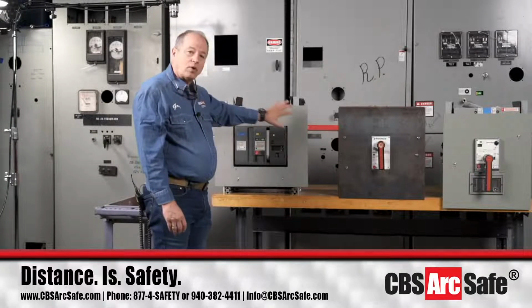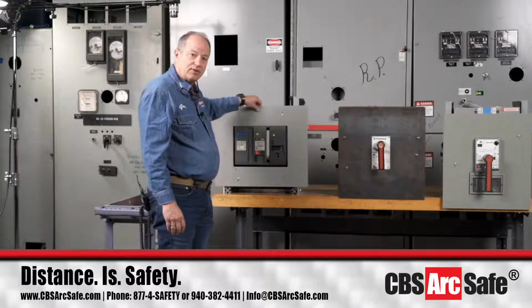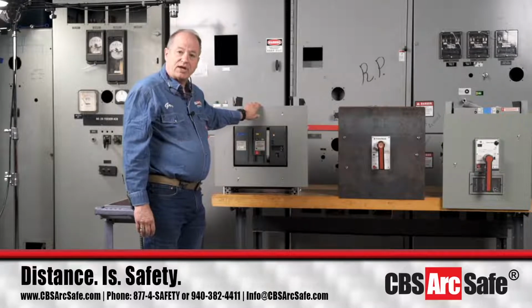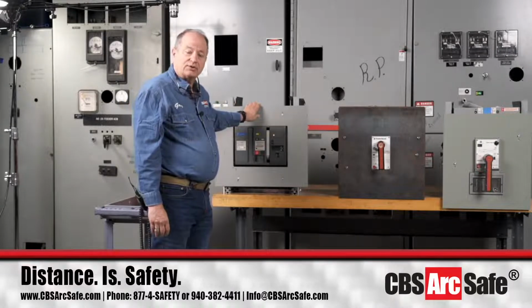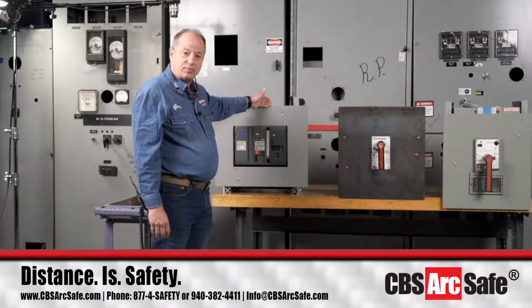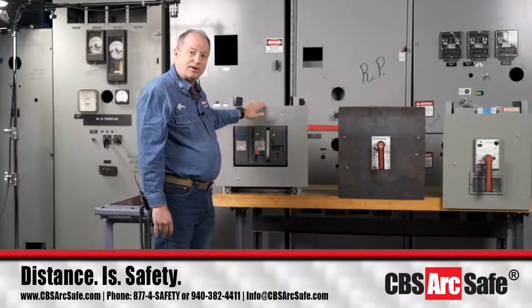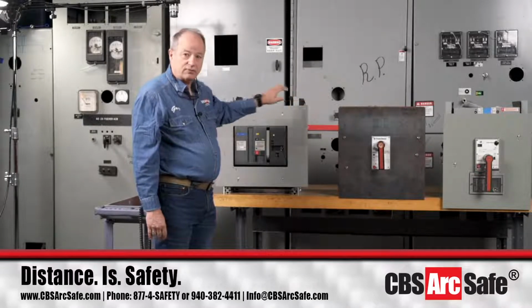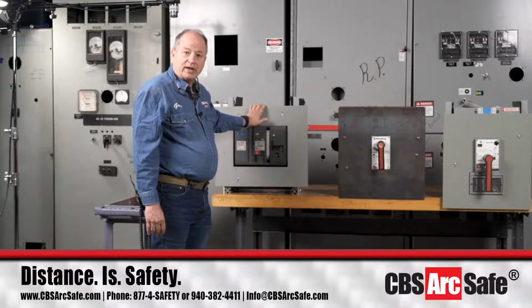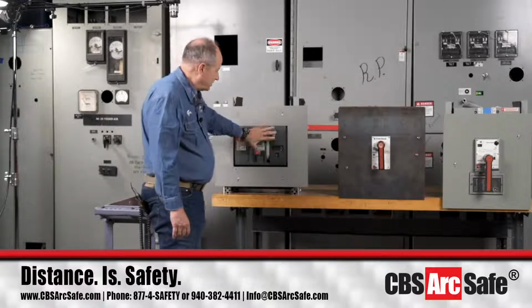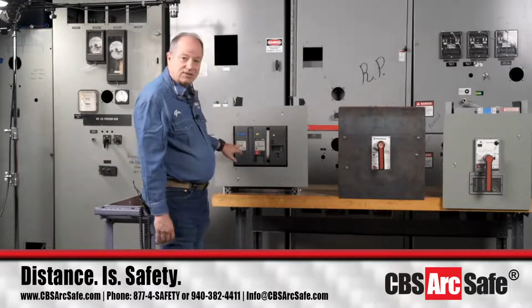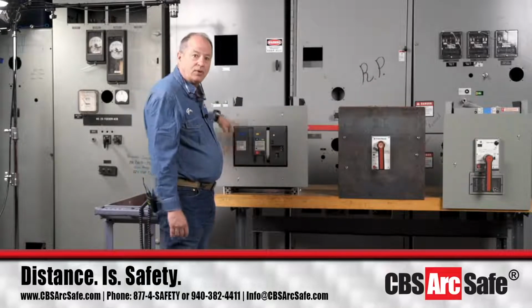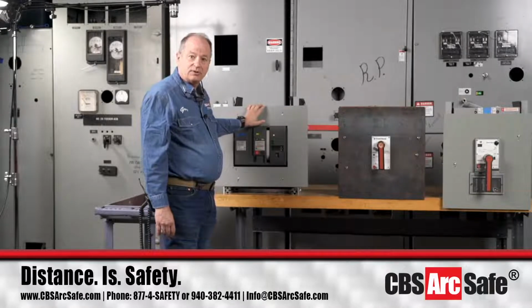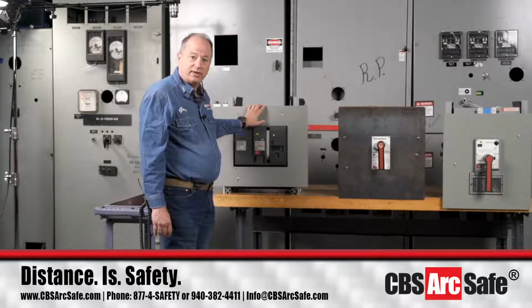If you have a big door with vents all over the place where this metal is going to flex a lot, we have a variation for opening the door, mounting it to the back frame of the circuit breaker, having it fit around the face, and being able to operate it that way. So how this circuit breaker is mounted, along with the large ones, can determine which actuator you need. Pictures and measurements are important. Don't just send us a picture of this little face that says SSD such and such on it - we really need to see the full picture of how this is mounted in the switchgear to know we're quoting you the proper equipment for your needs.